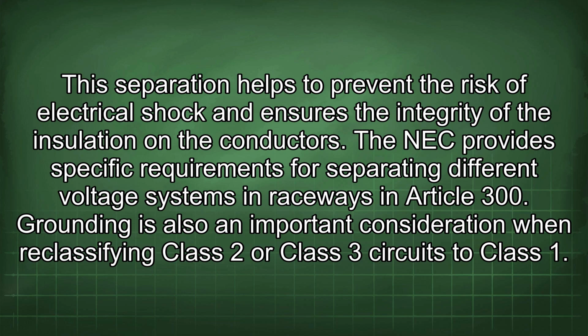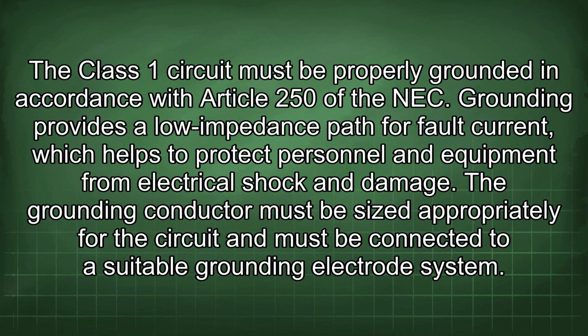Grounding is also an important consideration when reclassifying Class 2 or Class 3 circuits to Class 1. The Class 1 circuit must be properly grounded in accordance with Article 250 of the NEC. Grounding provides a low impedance path for fault current, which helps to protect personnel and equipment from electrical shock and damage. The grounding conductor must be sized appropriately for the circuit and must be connected to a suitable grounding electrode system.